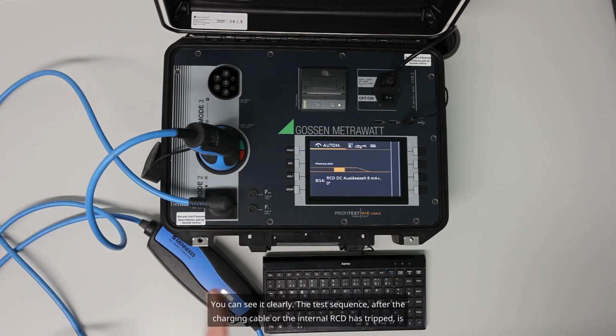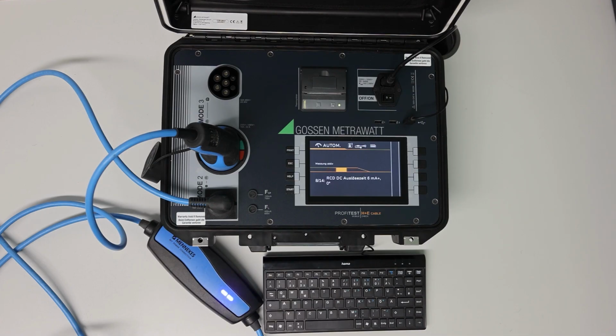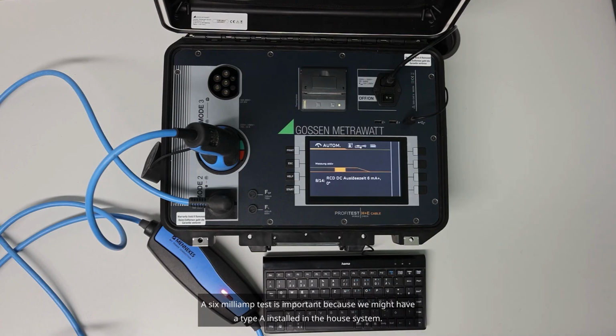The test sequence after the charging cable or the internal RCD has tripped is simply that it's switched to de-energized again, and then the process starts from the beginning. And that's how we can perform every test step by step. And you see, after the RCD test, the sensor system is up for testing. An important point. And now we can test the 6 milliamps here. And then you'll ask, why is a 6 milliamp test important? A 6 milliamp test is important because we might have a type A installed in the house system. And if I have a type A integrated, then it would go into saturation with DC fault currents greater than 6 milliamps. That means it would become blind.